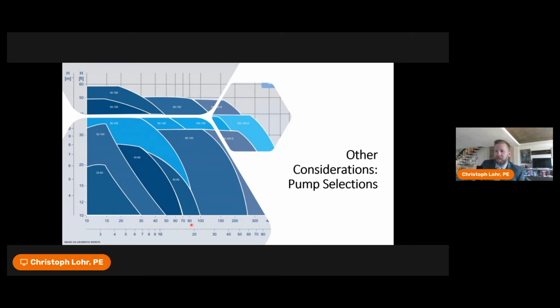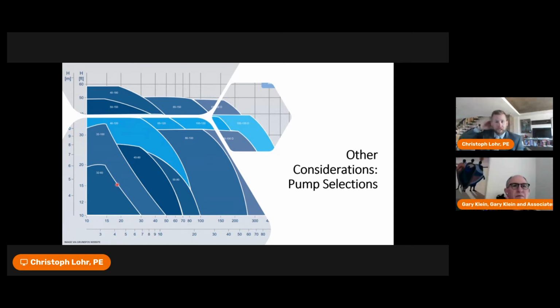But again, because of the parallel nature, my sense is that you're going to want to see 100% flow at all times. But the advantage of an ECM type motor is, let's say we selected a pump that had 15 GPM and 15 feet of head, and we utilized this 3260 curve here. Well, you still have wiggle room as you increase the flow rate. You can get up to 20 GPM, roughly, maybe a little bit less, under that curve with that pump. And these ECM VFD type pumps have the ability to select a pressure set point rather than swapping out the entire pump. This was a solution when I was on the engineering consulting side that we used to retrofit an existing hot water return system for a facility that was having hot water delivery issues.